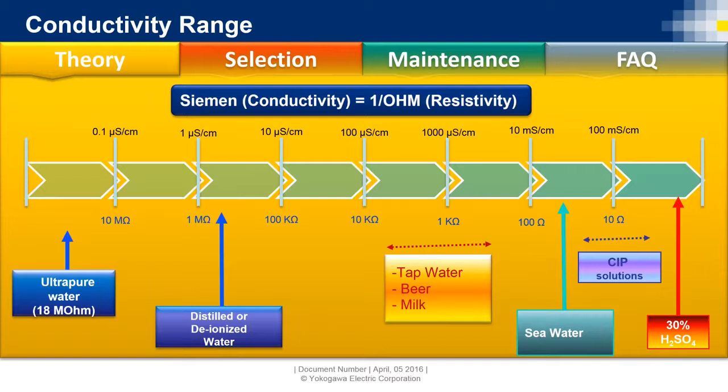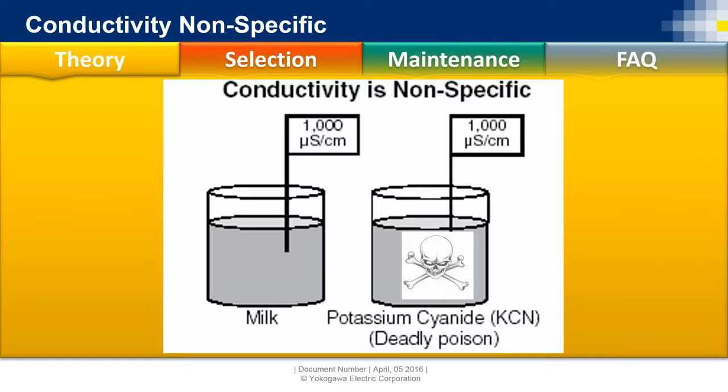Conductivity is simply a quantitative measurement for every ion that's present in there. It's not particular, and we cannot distinguish and tell you how many sodium ions are present versus something else. So I just have to be cautious of what we're measuring when we measure conductivity. And this is just going to show you an example.